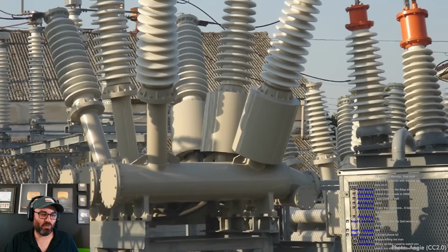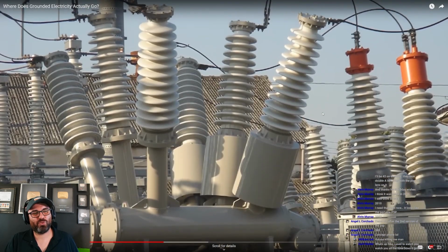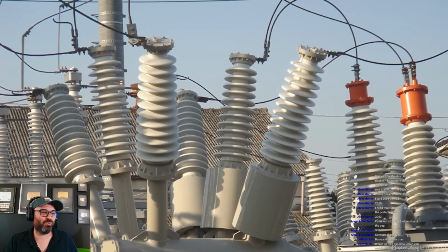The simplest way to do that is make sure the fault current is much higher than normal loads. In the case of a damaged toaster, something like that, fault current flowed through a conductor that's called ground, but is actually just a parallel wire that connects to the neutral in your electrical panel. So the grounding wire in the toaster has less resistance than you will.